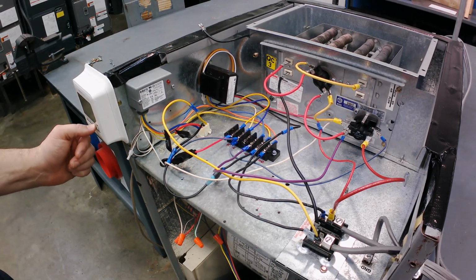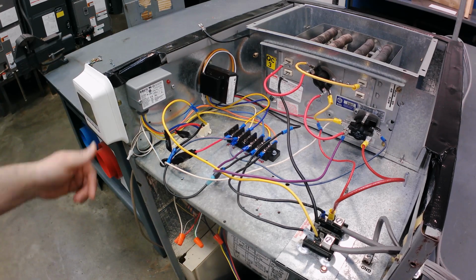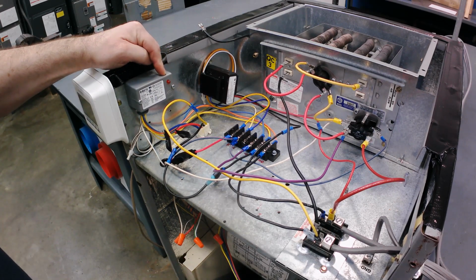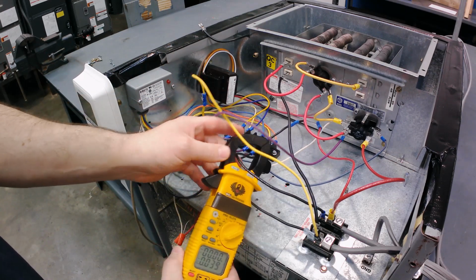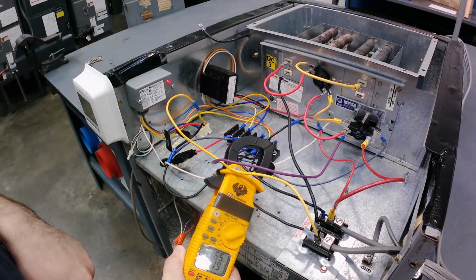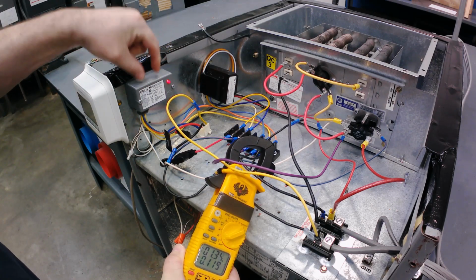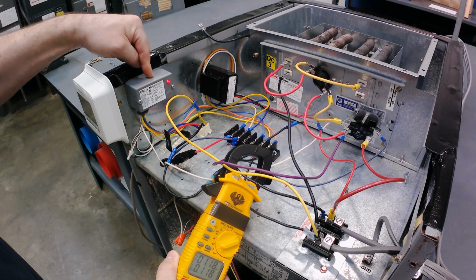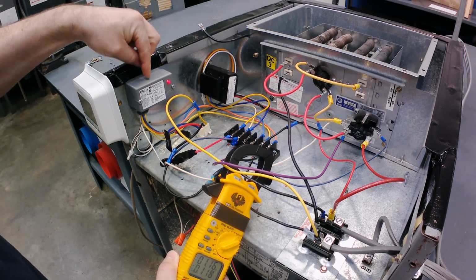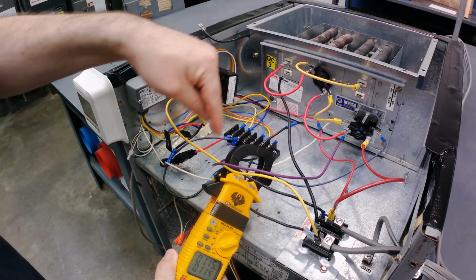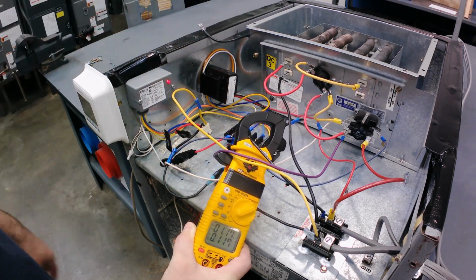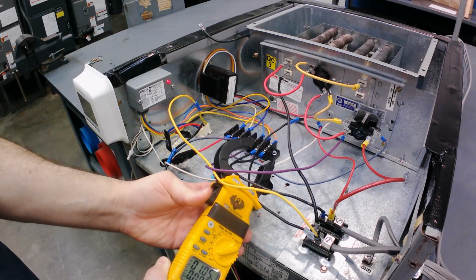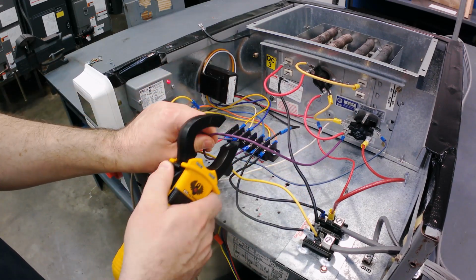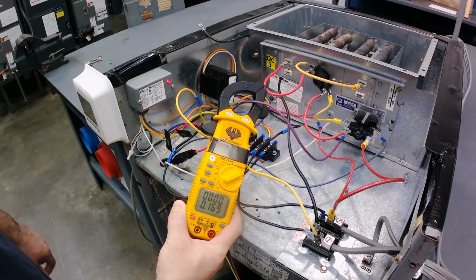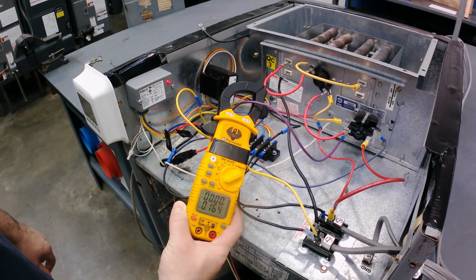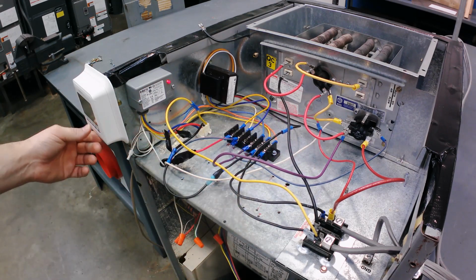So now I'm just going to turn the fan to the on position at the thermostat, and what you're going to see is this LED is going to light up. We're going to start pulling amp draw through the normally open switch, and we just got voltage to the coil, and that caused the switches to move inside this relay. So we are doing power through the normally open and out the common, and you can see we're pulling 1.2 amps or so. There should be nothing on this one. That's the normally closed circuit through the rib relay, and there's no power there.